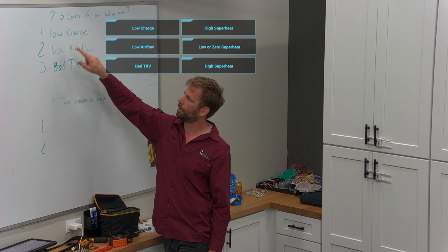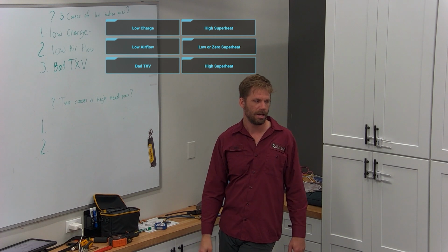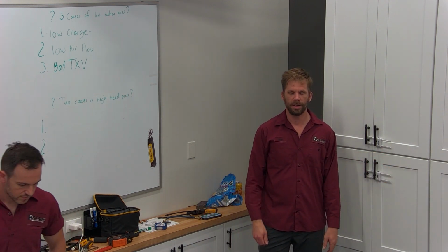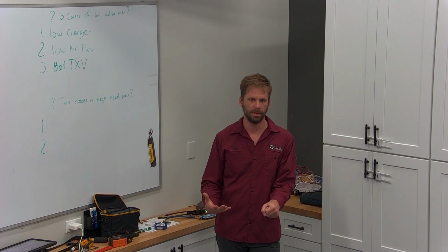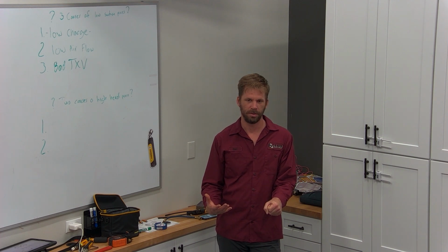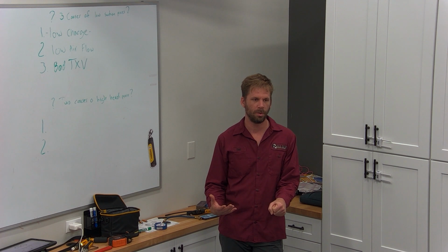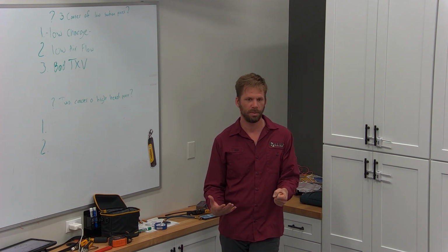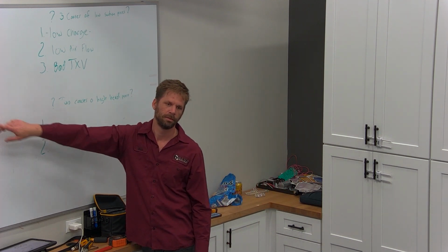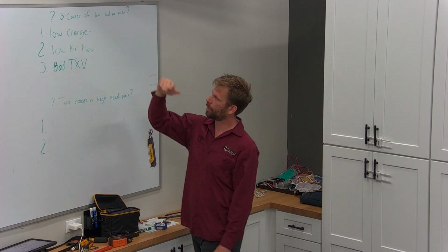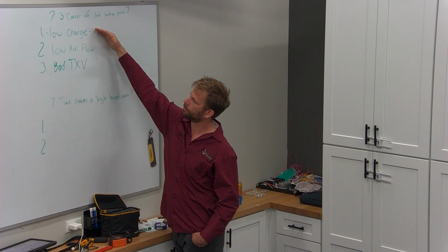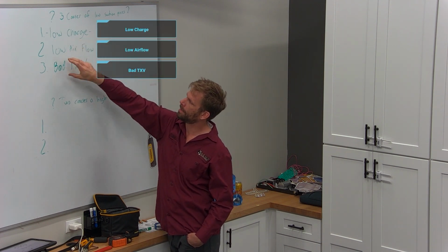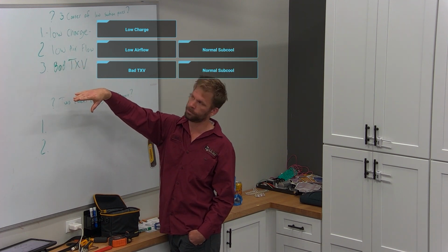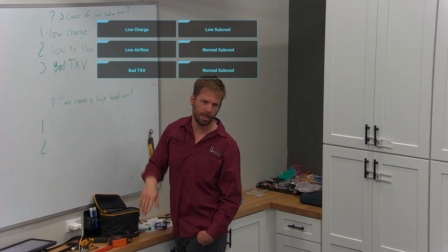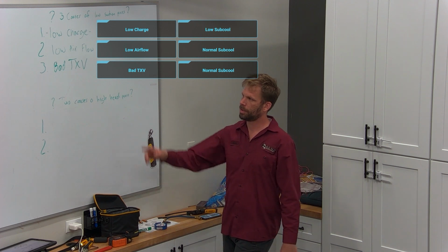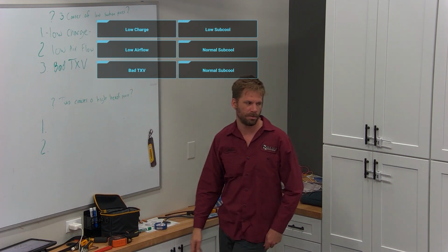So low airflow, low superheat, cold suction line. I said earlier, when his panels are off, if you walk up and your gauges show you really low pressure and you grab the suction and it's icy cold, it's not low charge. You have low airflow. But if you grab that suction and it's hot or warmish, not as cold as it should be, then for some reason we're not getting enough refrigerant into the coil. So cold line versus warm suction line. In low airflow and bad TXV, you're going to have a normal, pretty good subcool. Only in low charge will you have low subcool. So subcool is the indication of charge, and suction line temperature is the indication of airflow versus refrigerant.